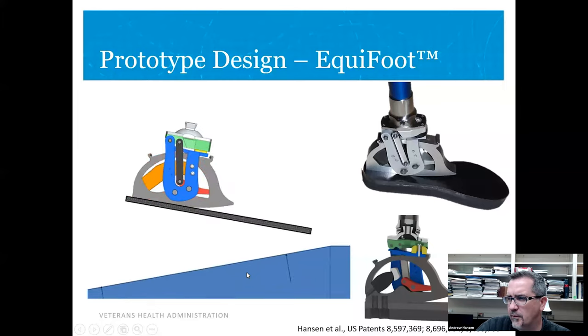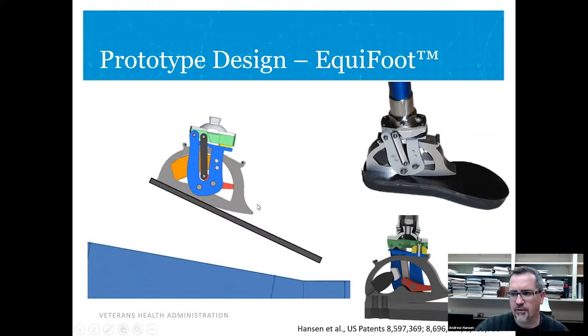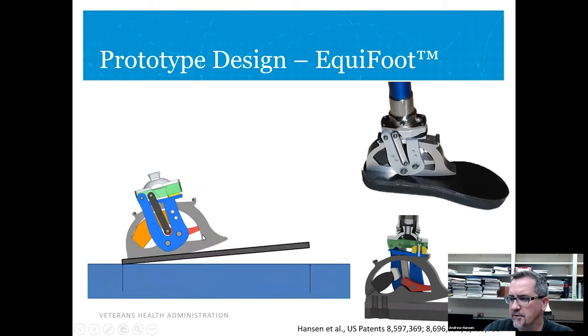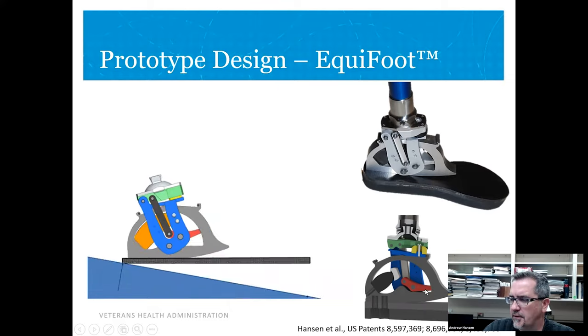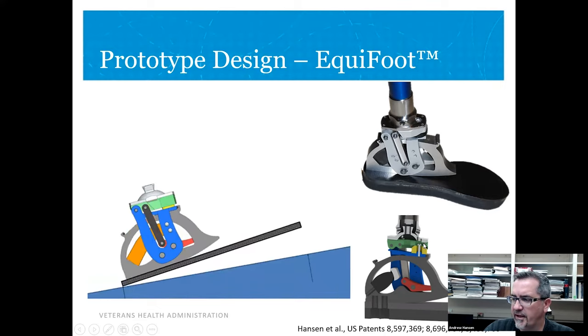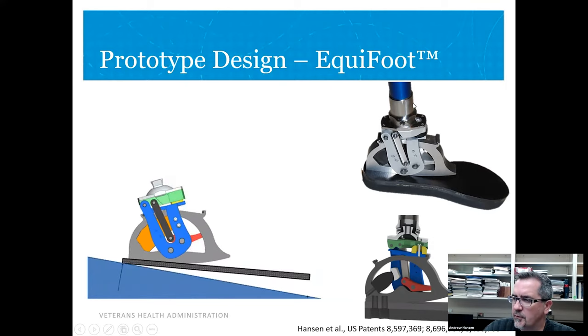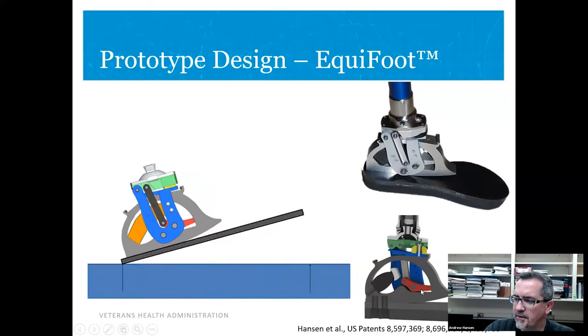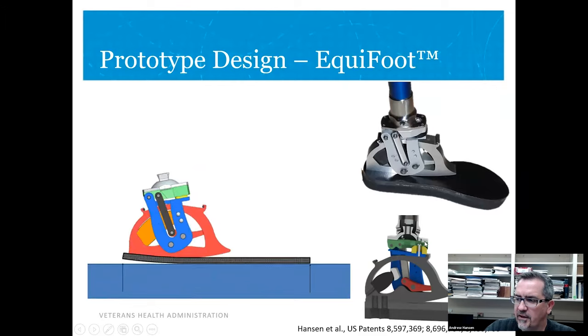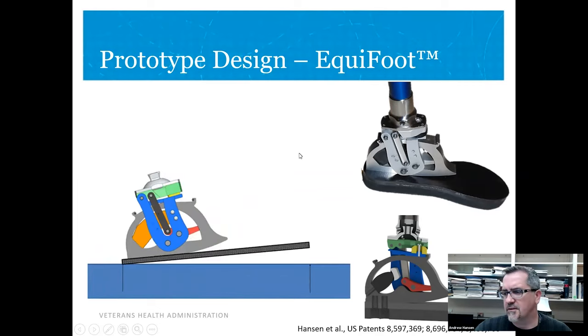We went through many different design iterations. This is about the third or fourth iteration built here at the VA in Minneapolis. It's a purely mechanical system. There's a cam lock system here — basically a one-way clutch that's weight activated — and then the neutralizing element is in the back. When someone steps down, they push this down, it brings the cam up into the ring and now it's a one-way clutch. When they take weight off of the limb, that disengages the clutch.